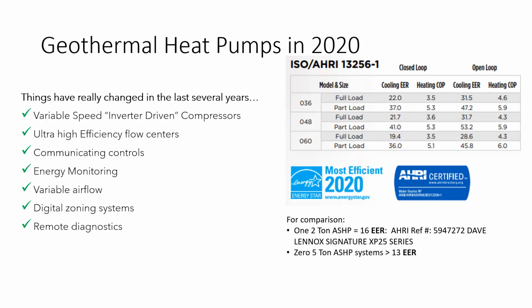Will it remove moisture? Yeah, a variable speed compressor with a variable speed fan is the ultimate solution for dehumidification. A variable speed geothermal unit can run at 20% capacity, meaning a 5-ton system can act like a 1-ton system with matching airflow.